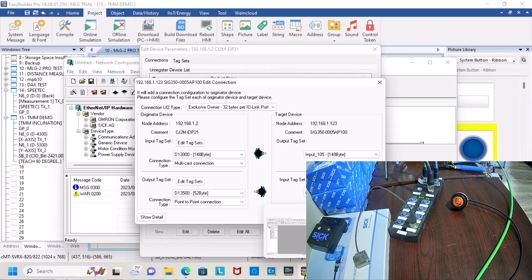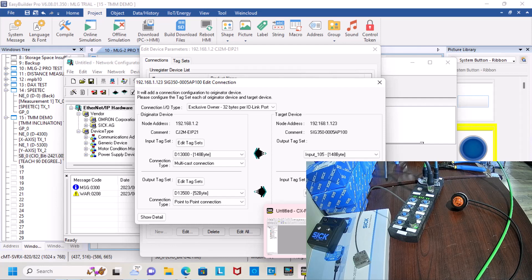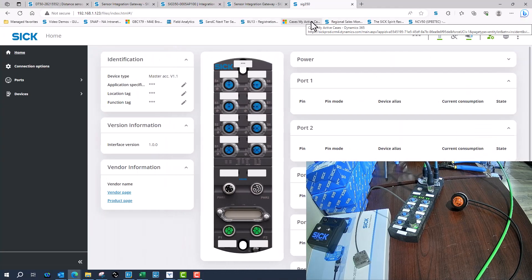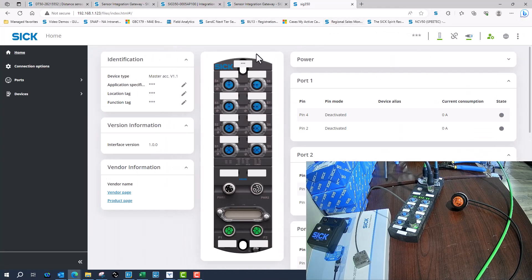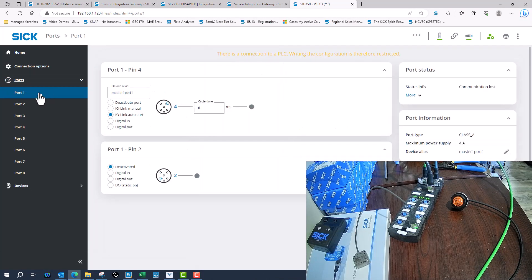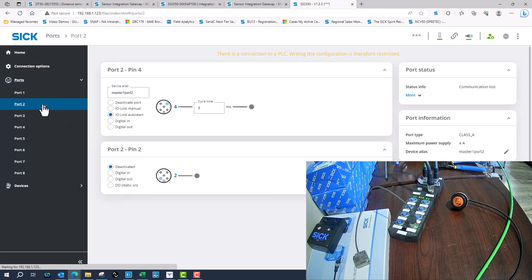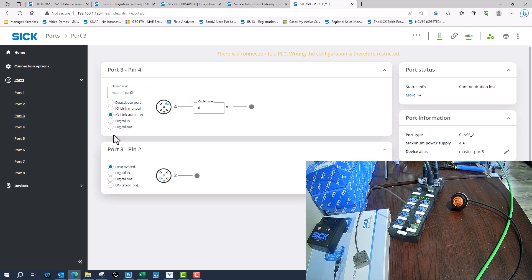Now, under the connection IO type I've got it set as without configuration. If I had it with configuration, when I connect a PLC to it then it would erase all of my settings. So even though I go through and set all the digital outputs, as soon as we cycle power and the PLC is connected to it, it would erase all of the settings and it would go back to default.